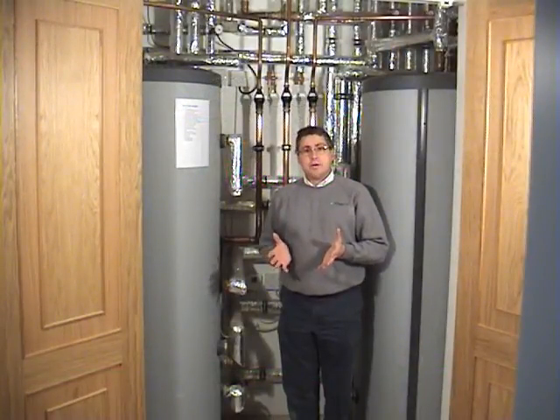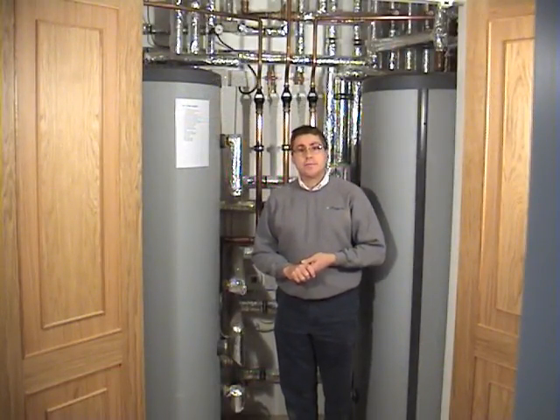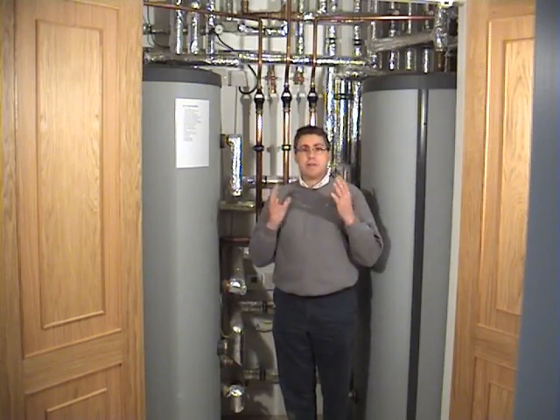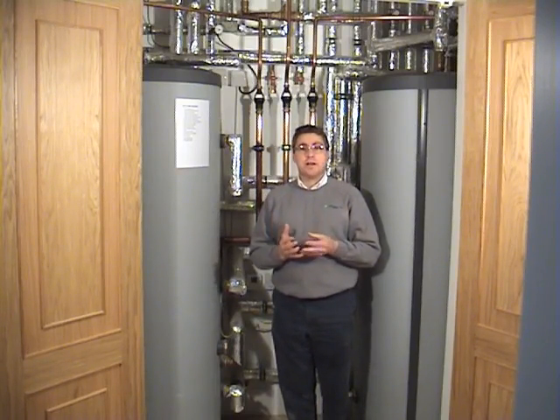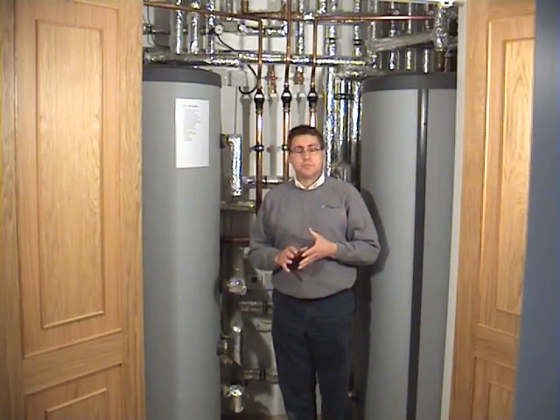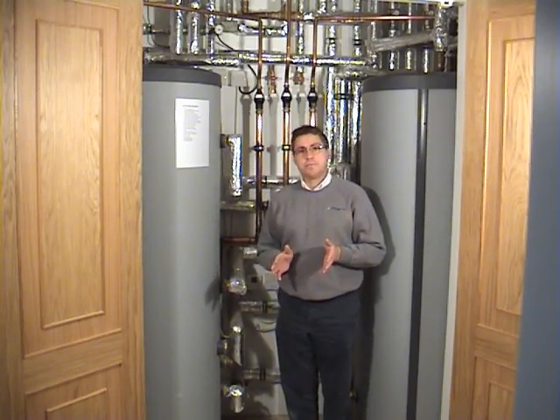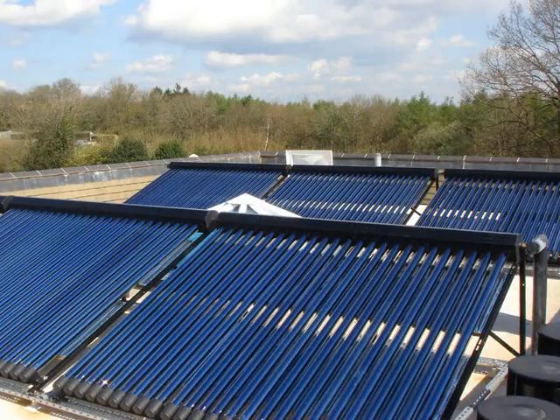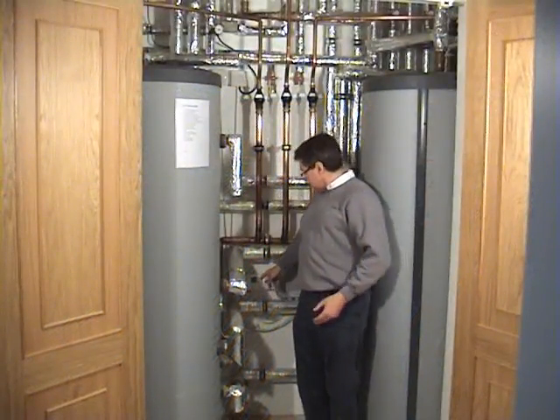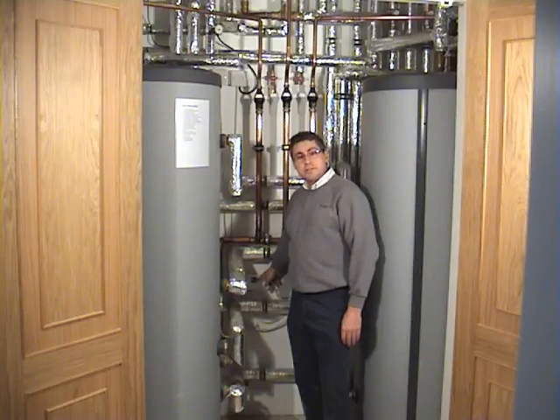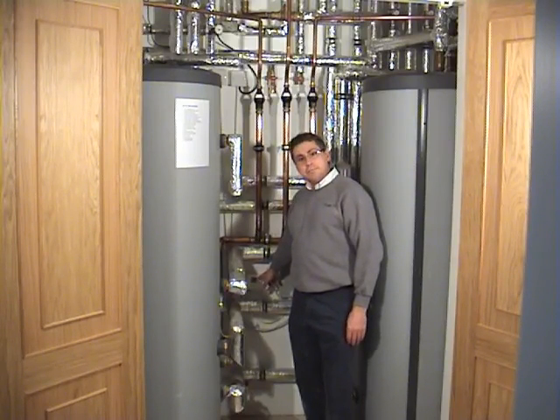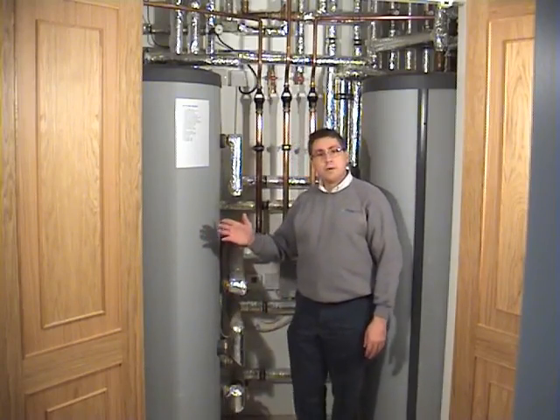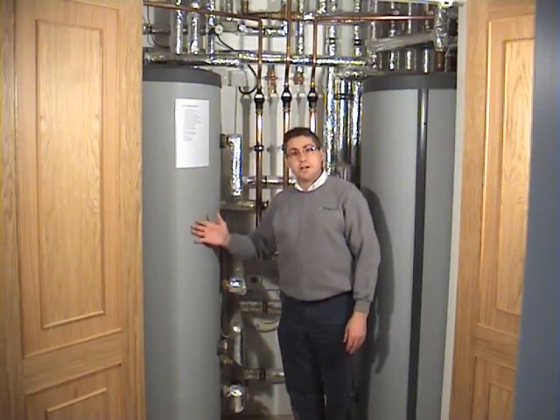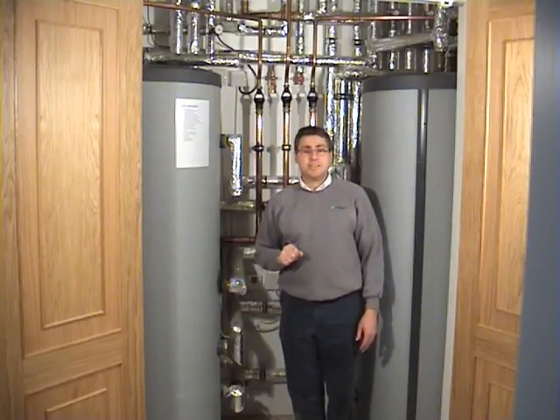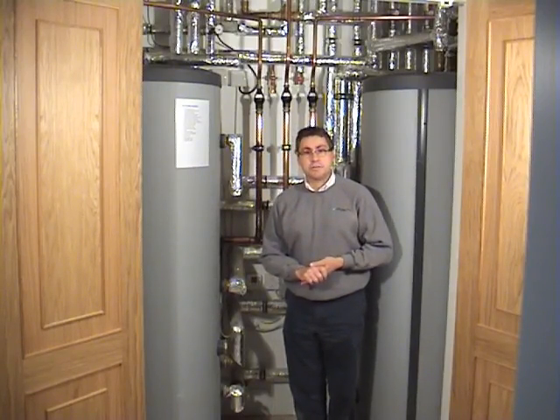Okay, we're with the hot water tanks now. There are two 450 litre tanks of usable hot water, each surrounded by 300 litres of water in which we heat it, so in total that's 1500 litres of hot water stored. The primary source of heating is of course the solar, coming down through the pipes at the top here. At the moment, on this spring day, there's 50 degrees coming into the solar, so the solar panels are easily heating the hot water. When the hot water's been satisfied and is up to temperature, the heating gets transferred to the energy cells, and all the heat is stored there.